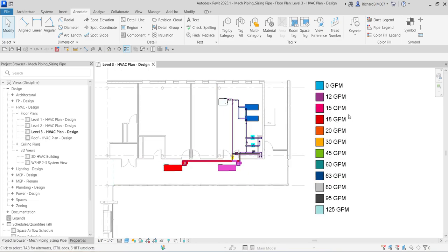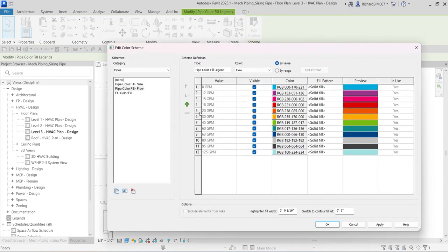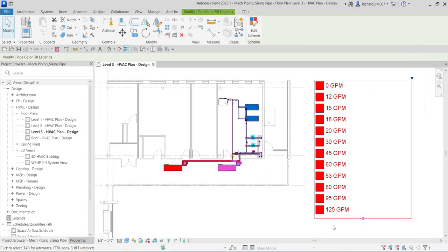You can check this legend to compare the color coding in the drawing and verify that flow values are as expected. To edit the color fill legend, select the legend and click 'Edit Scheme.' In the Edit Color Scheme dialog, make sure 'Pipes' is selected, then choose 'Pipe Color Fill Size' and click OK. This display will help you size the pipe using the friction and velocity sizing method.